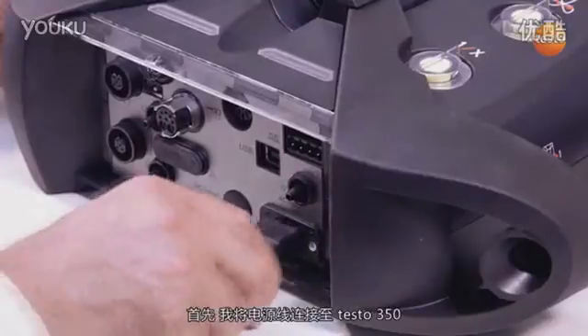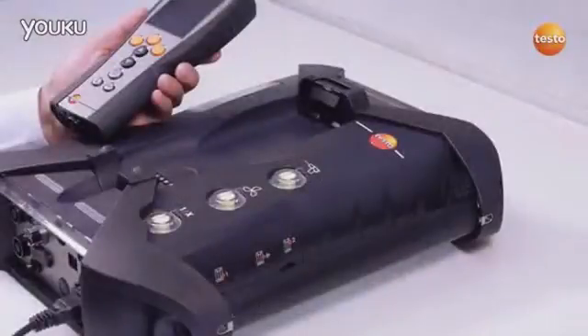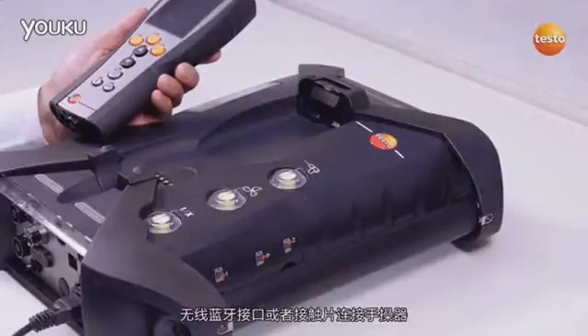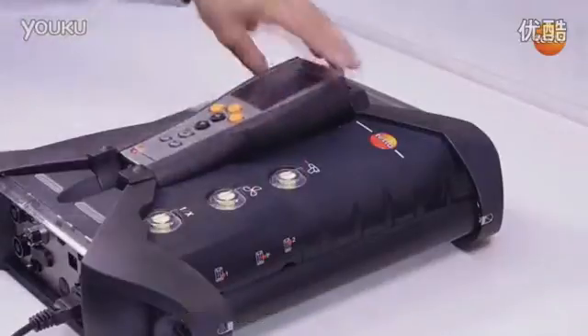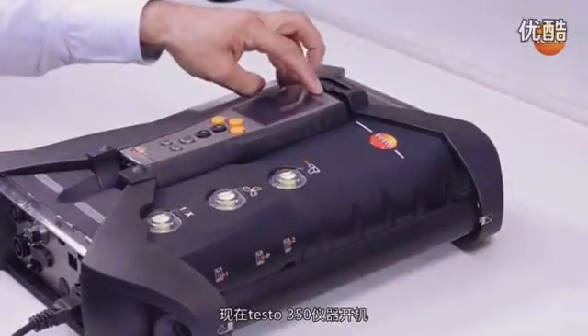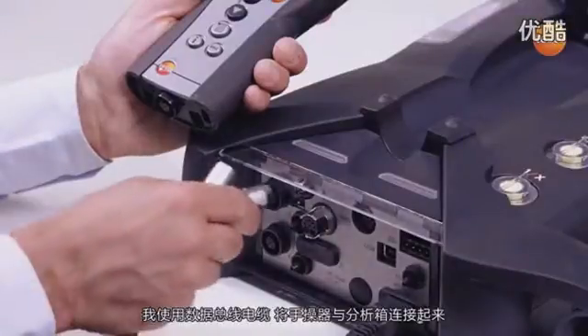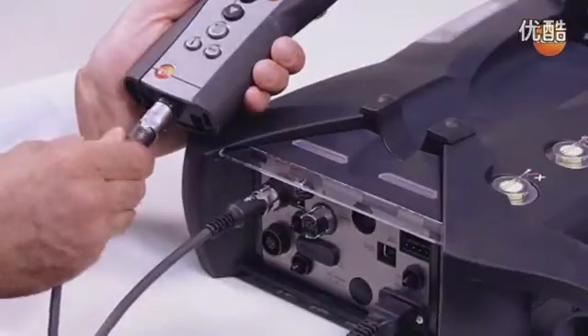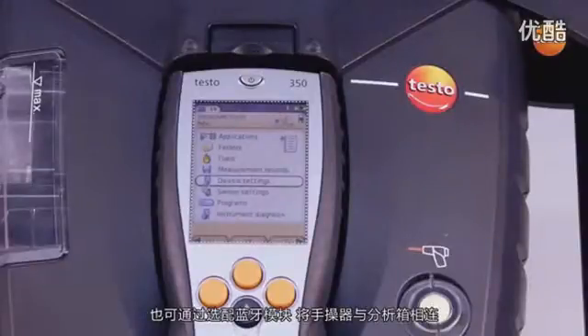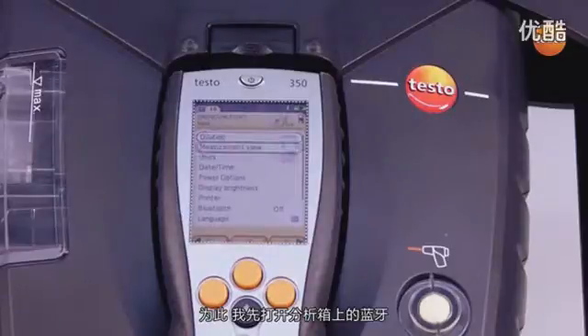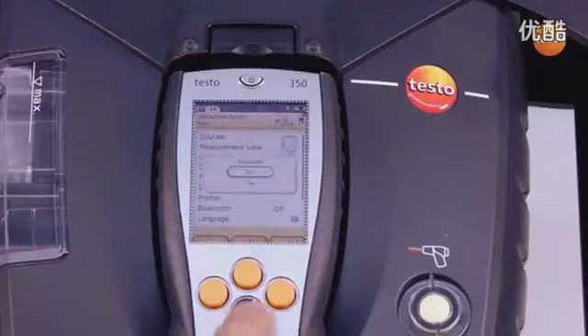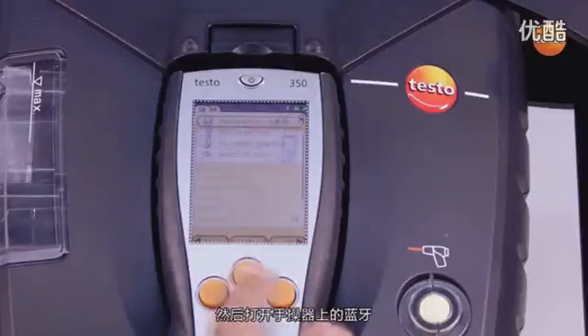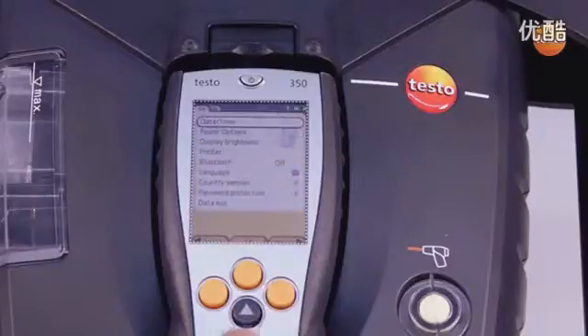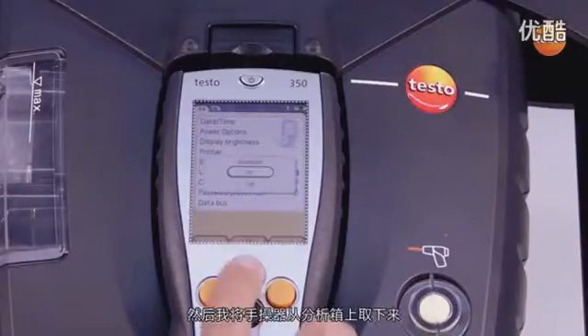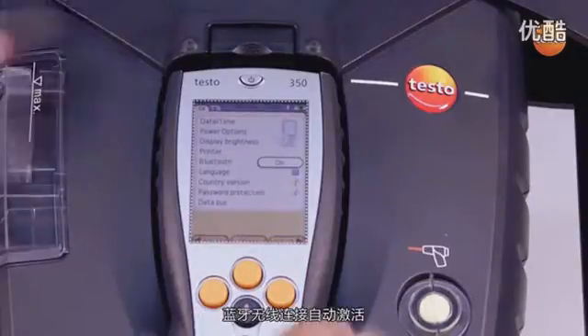First of all, I connect the power cable to the Testo 350. The control unit can be connected either using the data bus cable, the wireless Bluetooth interface or the contact bar. I now switch on the Testo 350. In order to make the data bus connection, I connect the analyzer box to the control unit. The analyzer box and the control unit can optionally be connected via Bluetooth. To do this, I first switch on Bluetooth on the analyzer box. I then switch on Bluetooth on the control unit. I can then remove the control unit from the analyzer box and the wireless connection is automatically activated.